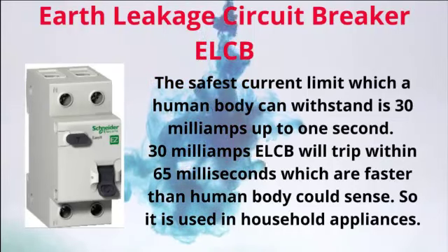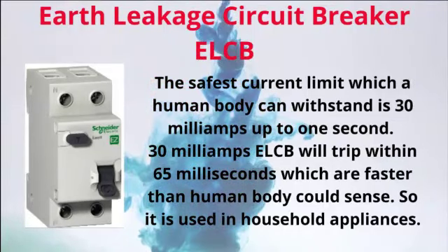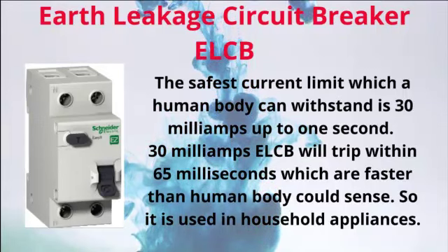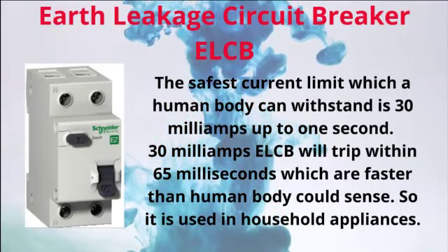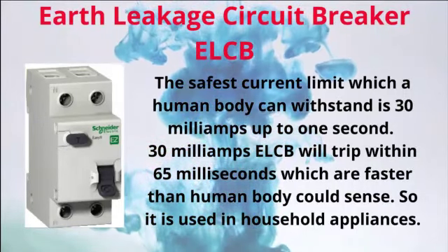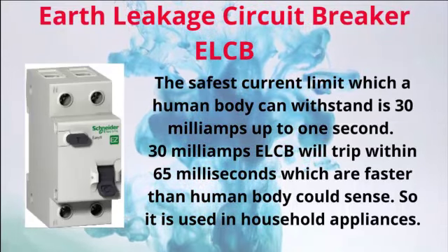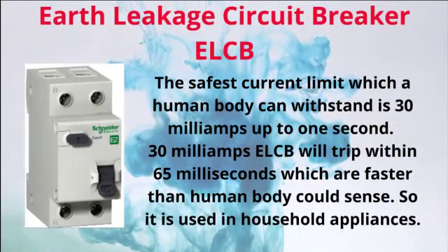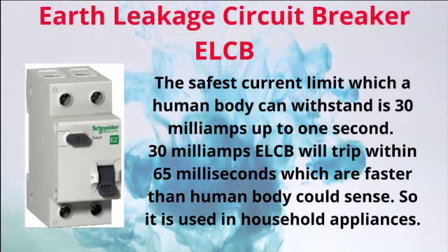The safest current limit which a human body can withstand is 30 milliamps for up to 1 second. A 30 milliamp ELCB will trip within 65 milliseconds, which is faster than the human body could sense. So it is used in household appliances.